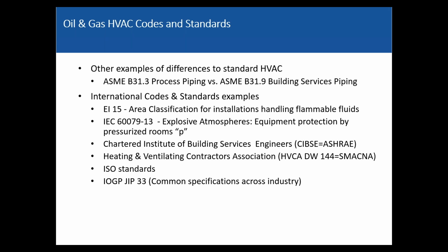Building services, B319 gets used. I don't know if we use it often, but that's one we would use. But in oil and gas, everything's B313. So you've got to be aware that if you have glycol piping for a heating coil, you're probably going to mate up to a different type of flange. You've got spec breaks you've got to deal with.